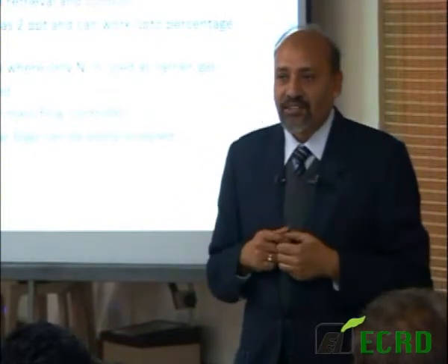They said initially that was the reason we went to PID, but we also find PID is a much better detector in terms of sensitivity, etc., for the aromatic compounds that we're trying to do with this system. So now it's just a PID that they sell with the benzene analyzer. They still have FID for some other analyzers, but for the benzene analyzer, they are just working with the PID. And it also implies that they just need nitrogen as a carrier gas when they are eluting it out from that trap into the column.